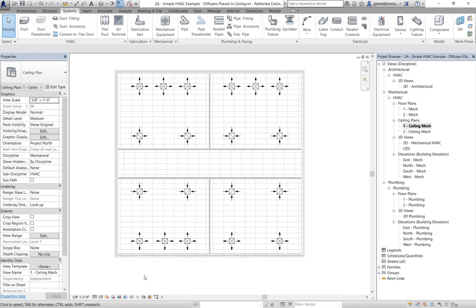If it's less than two feet, what happens is a supply and a return — which typically aren't on the same level, they're offset so they can pass each other — if each is a minimum of 12 inches, you'd need at least two feet. Less than that and things get really tight. Standard ceiling height in a room is about eight feet, some rooms are ten or eleven. Higher headroom feels better, but then you have to account for bigger ducts. You have to establish the space you want in the room, then figure out the remaining space for ductwork.